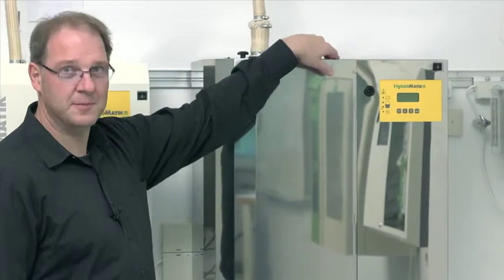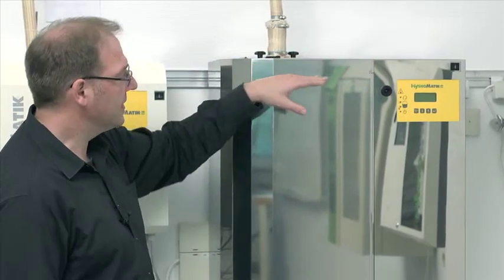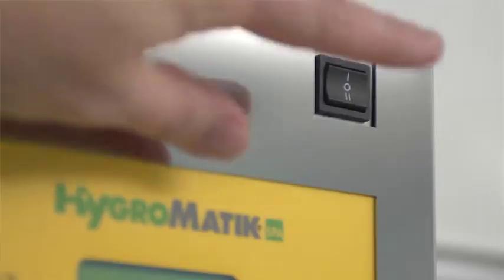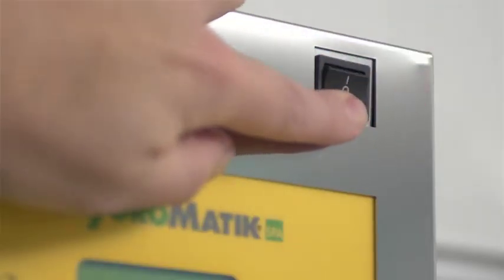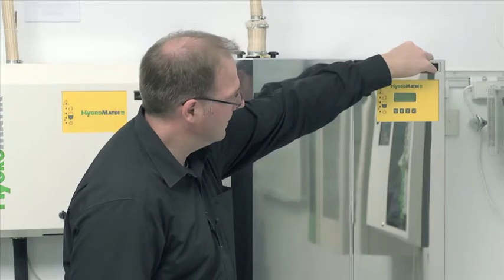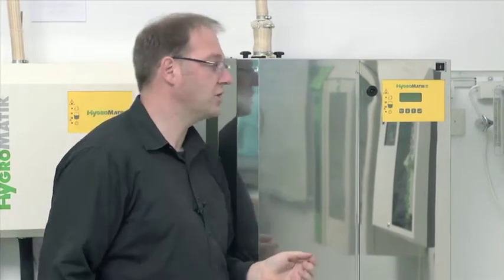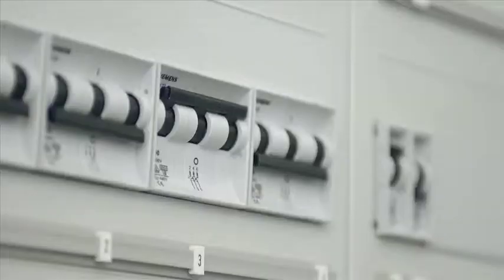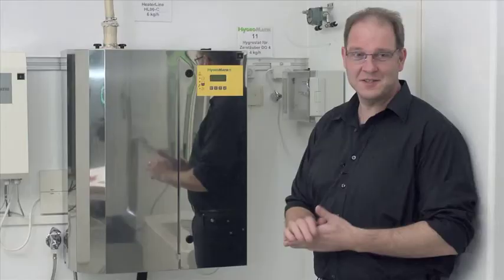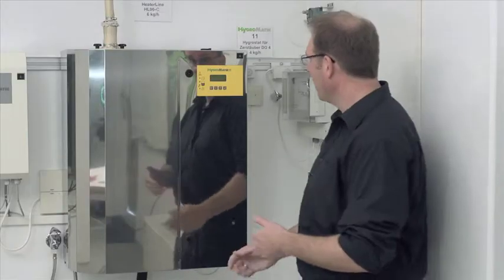Before I begin with the actual maintenance of the unit, I first need to make sure that the water is drained from the steam cylinder. To do so, I press and hold the control switch in position 2. After the water is drained, I disconnect the unit from the power supply and secure it against being restarted. You want to avoid being at the unit when all of a sudden the power could come back on.